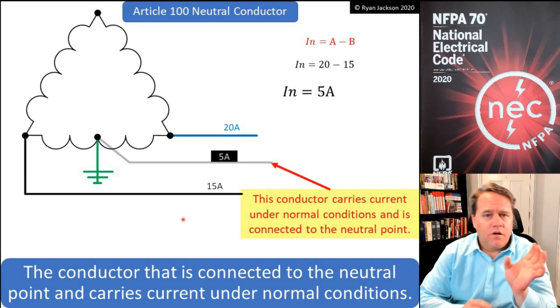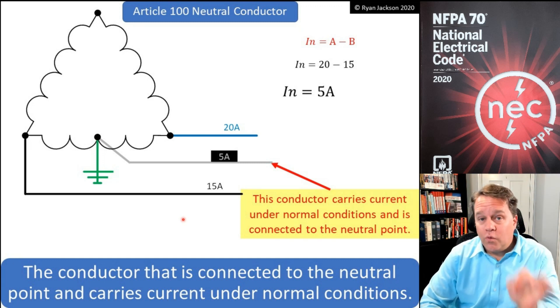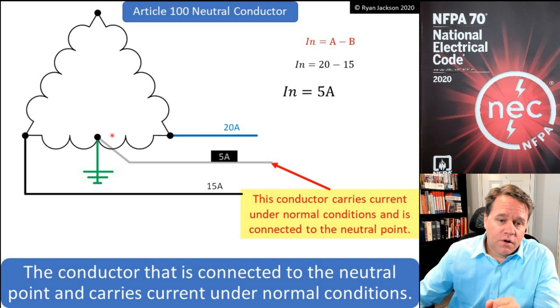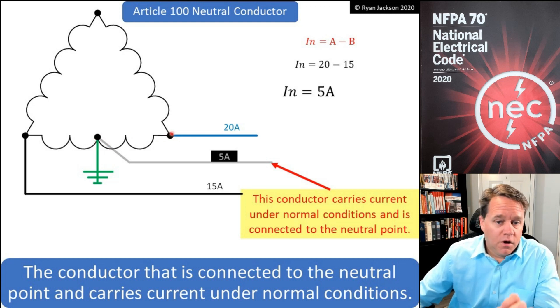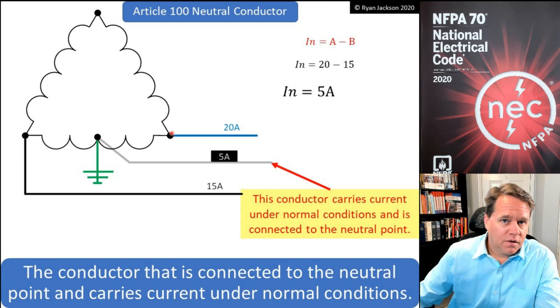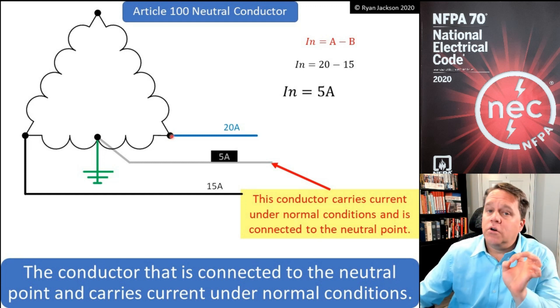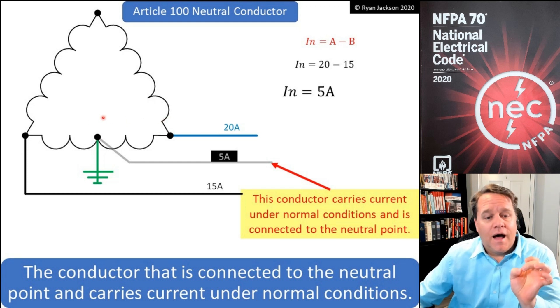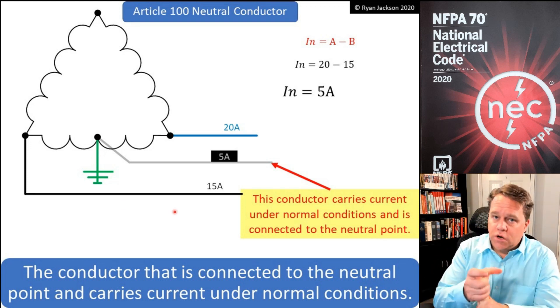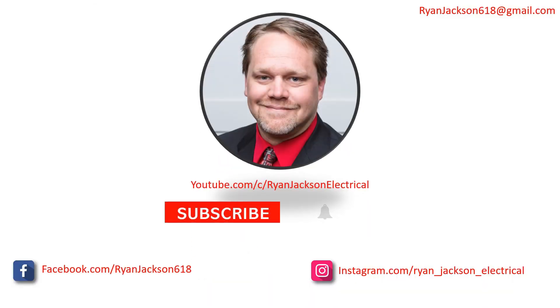What if I had a three-phase three-wire delta connected system? That would be a corner-grounded system. If I shift the grounded point over to a corner of the delta, that conductor would carry current under normal conditions, but it's not connected to a neutral point — because on a delta, a neutral point can only exist at the center of one of the phases. That's the difference between a neutral conductor and a grounded conductor.